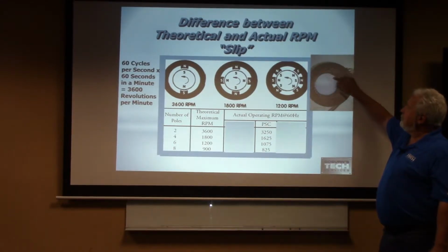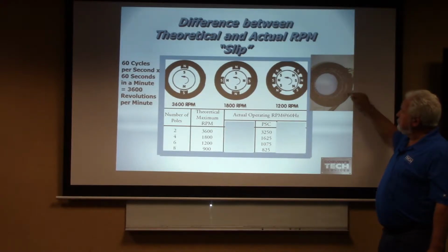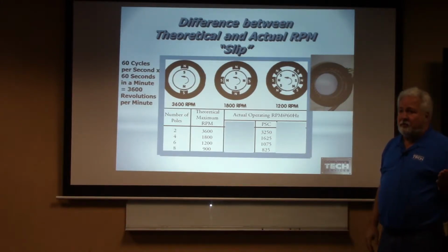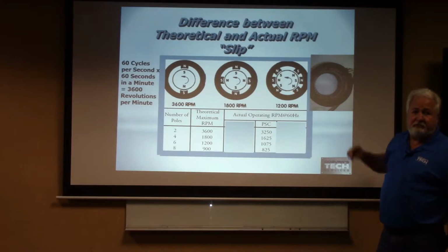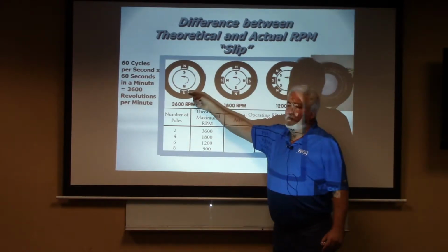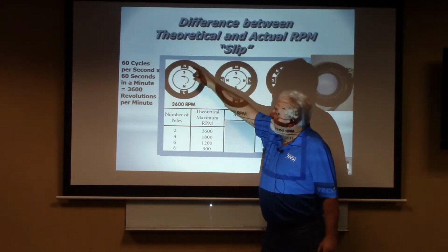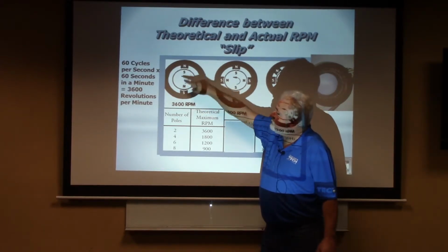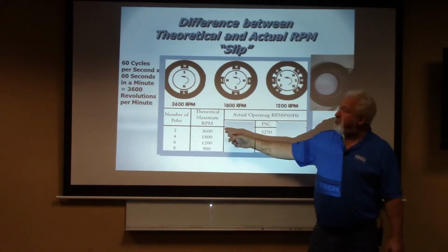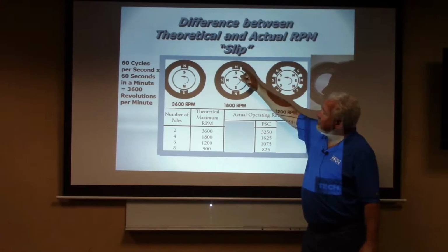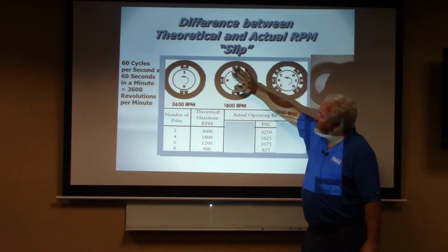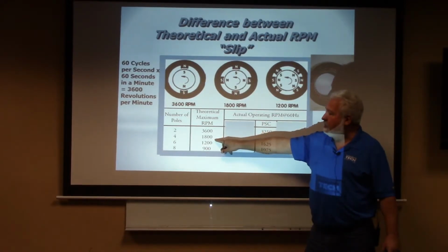If you'll look inside of a motor, you'll see that it's wrapped in different loops around in there. The more poles you have, the less speed that motor is going to have. But if you pull it out, you'll be able to see what the speed of that motor actually is. A 2-pole motor is going to electrically charge north and south every 60 cycles. 60 cycles per second means it's going to have a 3,600 RPM. If I have a 4-pole motor, it's going to shift from here to here, not all the way around. So it's only going to go halfway before it goes to the next one. So that RPM is now going to drop down to 1,800 RPM.